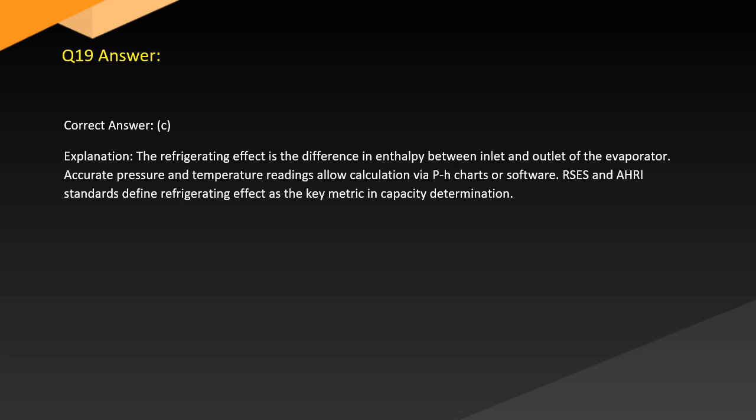Answer. Correct answer, C. Explanation. The refrigerating effect is the difference in enthalpy between inlet and outlet of the evaporator. Accurate pressure and temperature readings allow calculation via PH charts or software. RSES and AHRI standards define refrigerating effect as the key metric in capacity determination.